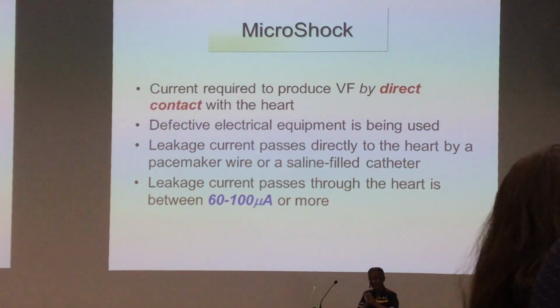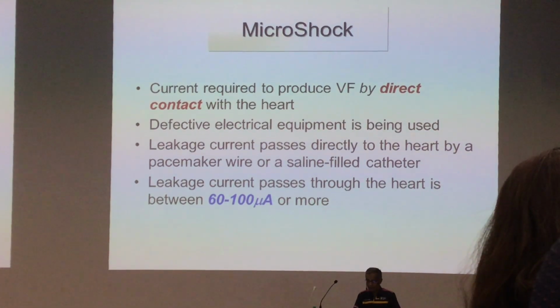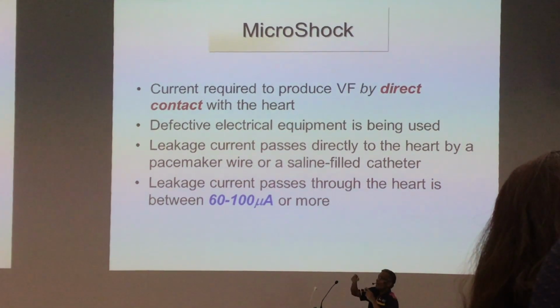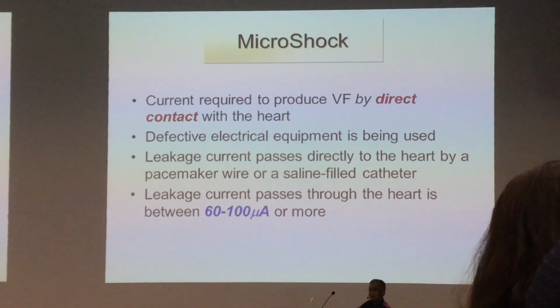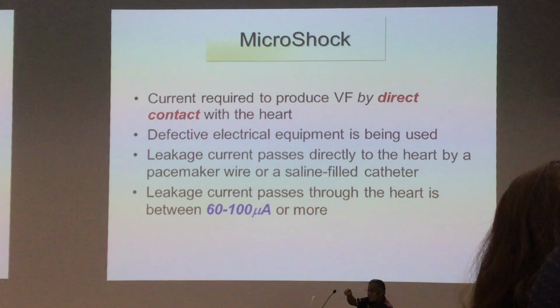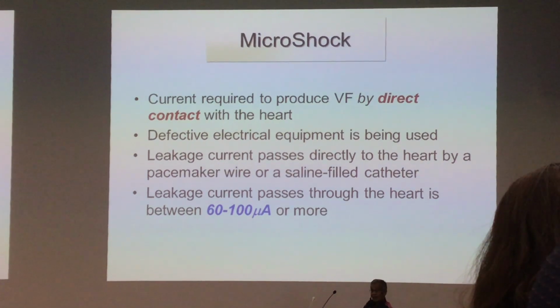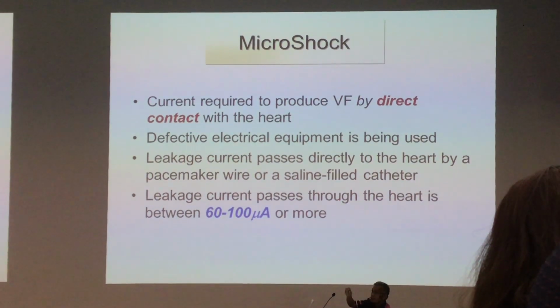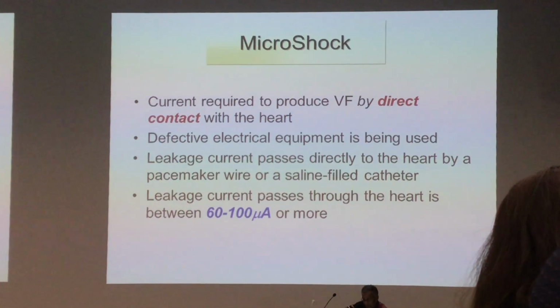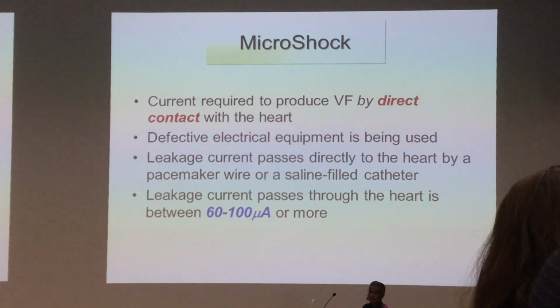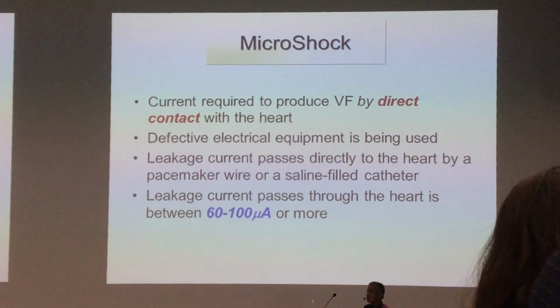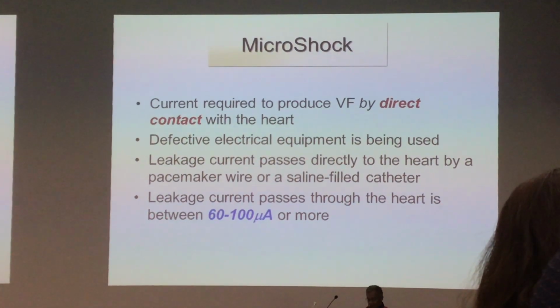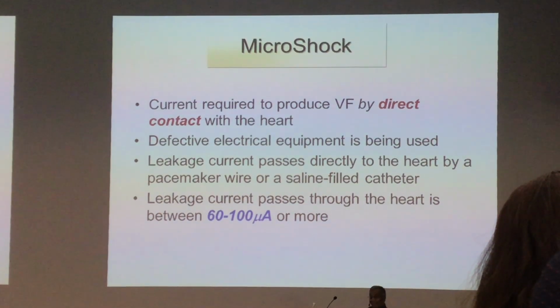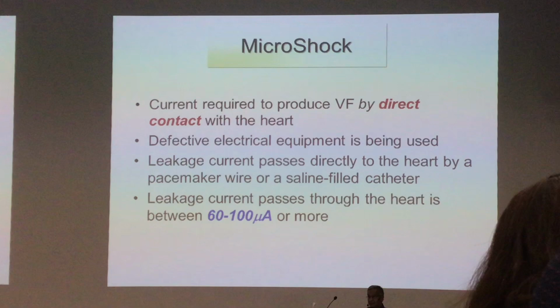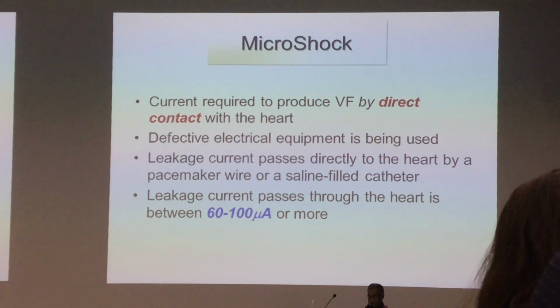So this is microshock, which means the current required is very, very low. Let's say your CVP line is in the RA. The machine is faulty. The current will travel from the faulty machine to the saline-filled catheter. Saline is a good conductor. So if 60 microamp goes from the faulty machine, to the CVP line, to the right atrium, he will end up with VF. That's why you have to be careful when you are doing cardiac procedures. You must do it in Class CF. This is important, all right?